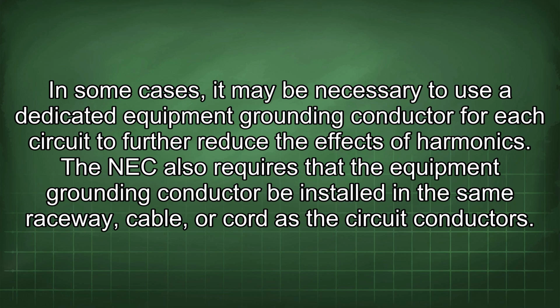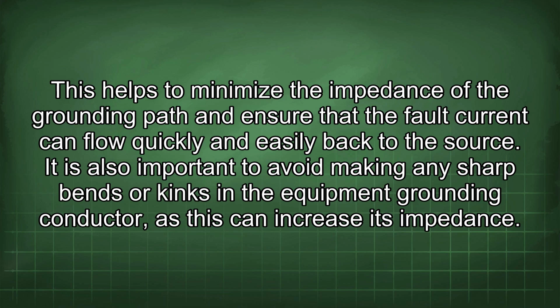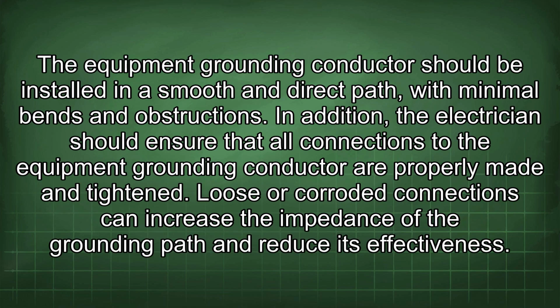The NEC also requires that the equipment grounding conductor be installed in the same raceway, cable, or cord as the circuit conductors. This helps to minimize the impedance of the grounding path and ensure that the fault current can flow quickly and easily back to the source. It is also important to avoid making any sharp bends or kinks in the equipment grounding conductor, as this can increase its impedance. The equipment grounding conductor should be installed in a smooth and direct path, with minimal bends and obstructions. In addition, the electrician should ensure that all connections to the equipment grounding conductor are properly made and tightened.